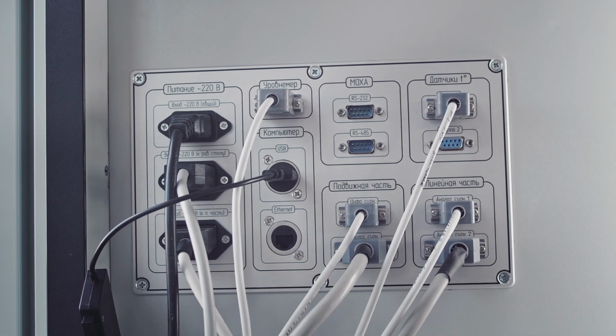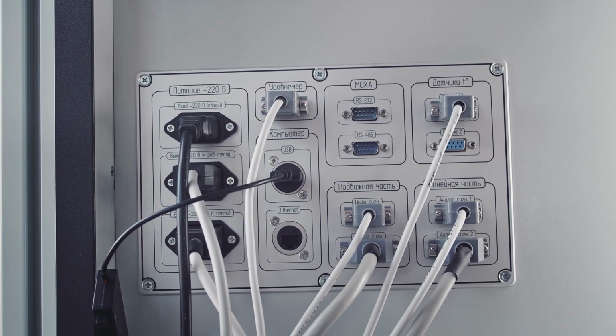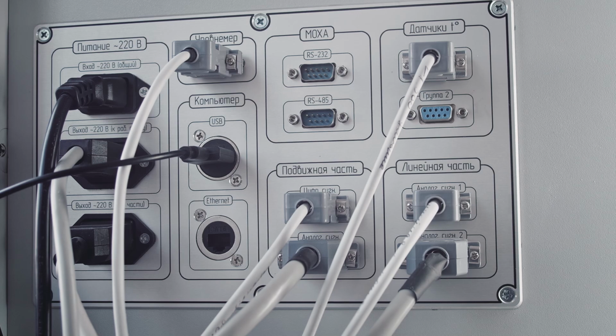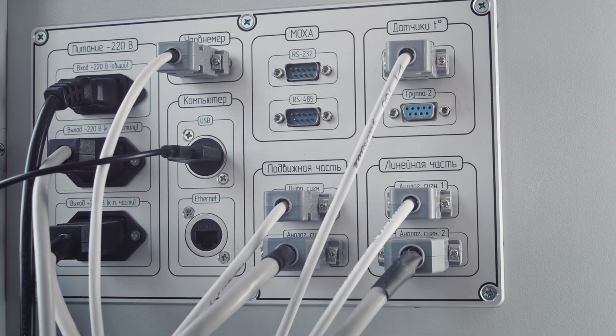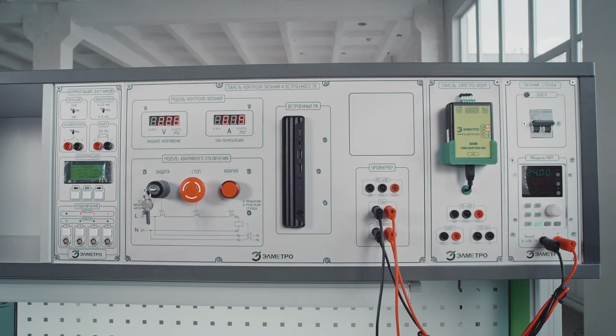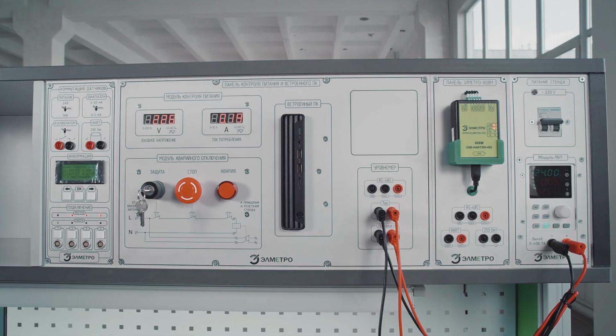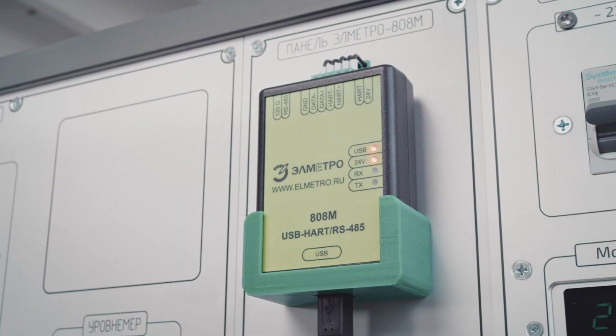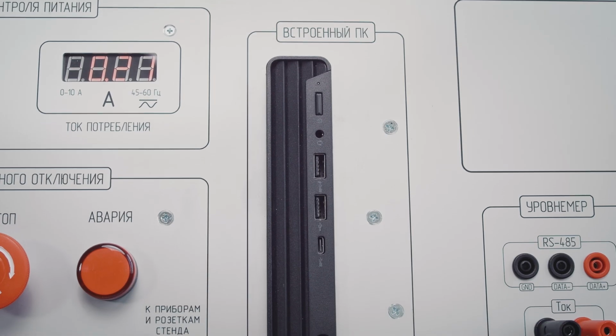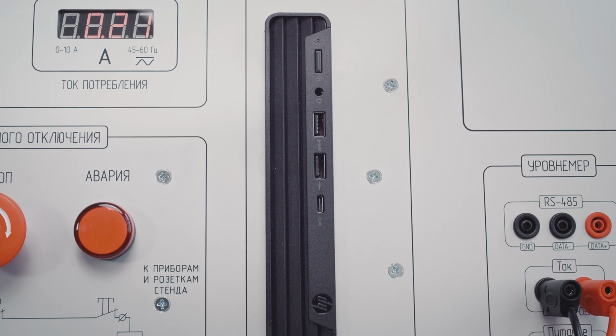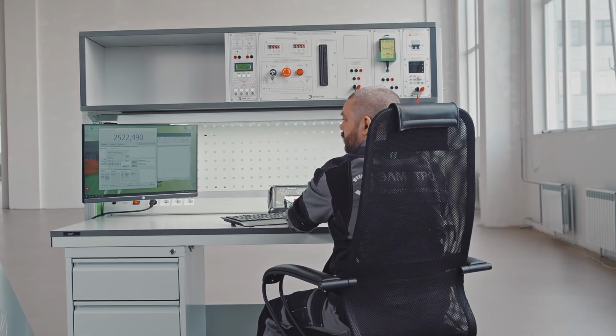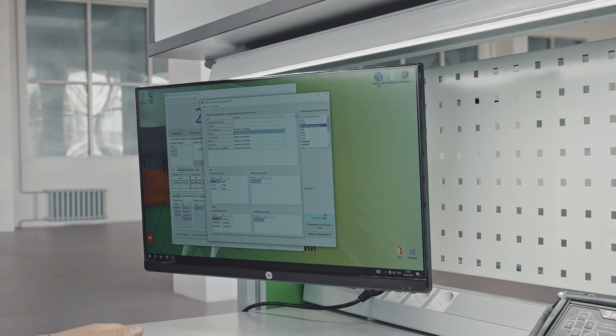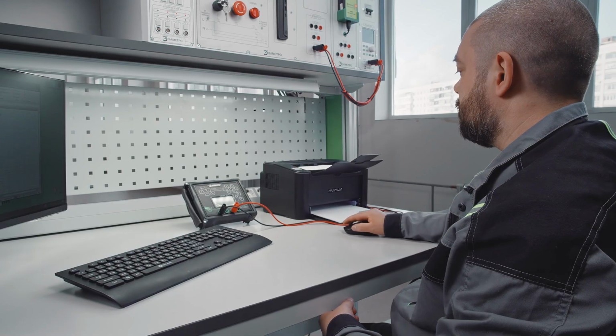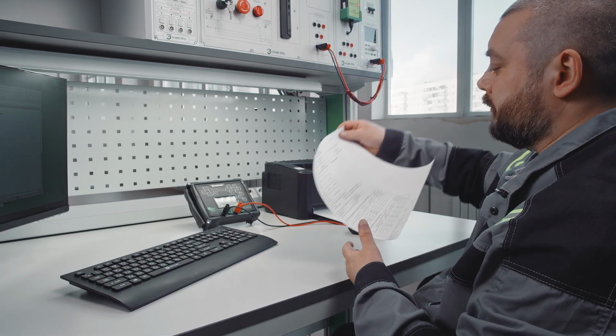On the reverse side, there are modules for connecting the bench to the 220-volt grid and communication of the operator's workplace with other bench assemblies. The measured parameters are transmitted via the RS-485 or HART networks. An inbuilt PC with pre-installed proprietary software controls the bench operation. It prepares the verification or calibration reports.